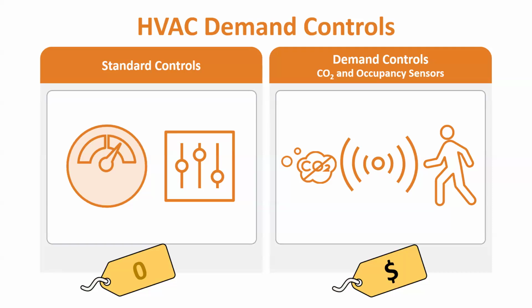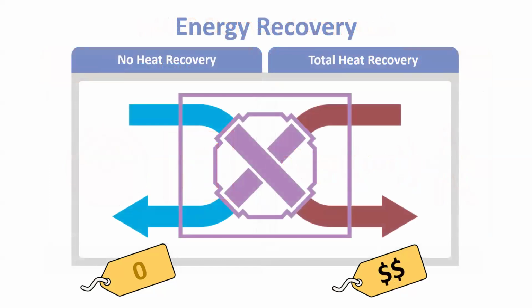Next, we've got our HVAC demand controls. In our base design, we have typical controls responding to the needs of various spaces based on temperature and maybe humidity. With our upgrade, we add demand controls, allowing us to cut back on ventilation rates and possibly setback temperatures based on whether spaces are actively being used or not. This could take the form of carbon dioxide sensors that kick in when high occupant loads drive higher CO2 levels, or occupancy sensors to detect movement. This is a fairly low cost upgrade, especially with occupancy sensors, because we can tie into the same sensors used for the lighting controls.